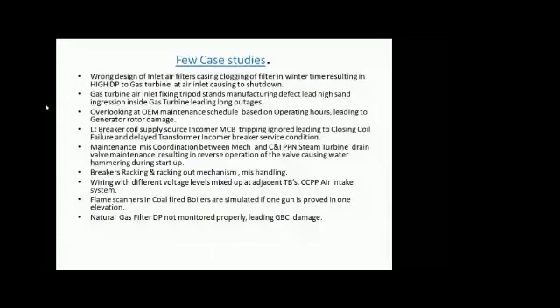Normally, after about 8,000 to 9,000 operating hours, or after 8 years, a generator of 200 megawatts and above has to be inspected. You have to pull out the rotor and inspect the stator windings. You have to inspect the rotor. Many tests are done after removing the rotor. Those things have to be seen by specialists, because nothing can be seen inside the generator except small parameters like winding temperatures and vibrations. There can be damages which are in a preliminary stage. So these OEM schedules should not be overlooked.